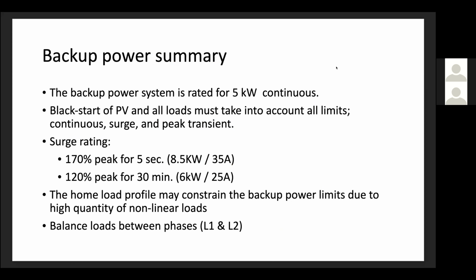So, quick summary then on backup power functionality. The backup power system is rated for 5 kW continuous. Black start of PV and all loads must take into account all limits: continuous, surge, and peak transient. If you can avoid the peak transient type loads, that's probably your best bet whenever possible. The others can be measured, and make note of the type of equipment that you'll need to do that.